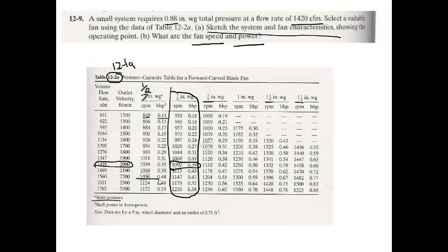That would be at this operating point. So if I keep the fan speed the same but increase my flow rate to 1560 CFM, I end up with a face velocity of 2200 feet per minute. Still at the same RPM speed, but with a different static pressure.